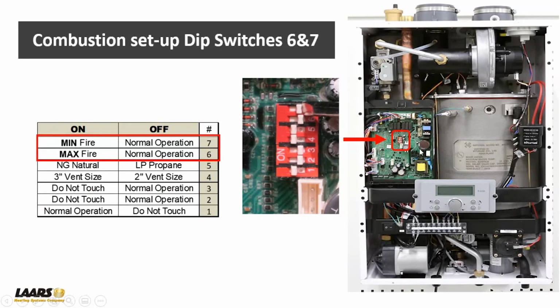On the dip switches. So here's our circuit board, dip switch 6 and 7. This is where you're going to lock a boiler into high fire or low fire. Dip switch 6 is your high fire. So for example, I would throw dip switch 6 to the on position, and that boiler will modulate right up. You can actually look in the sight window and you'll see your flame pattern modulate up. You're going to check your analyzer up here. You're going to take the plug out, put your analyzer in. You'll see this video in a minute. Check your CO2s. We'll show you those values.